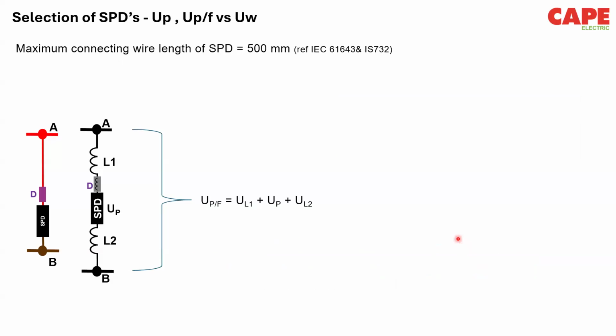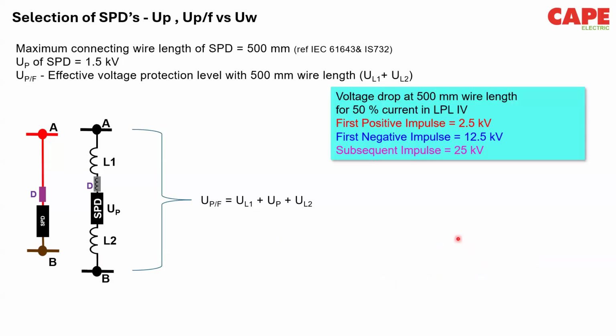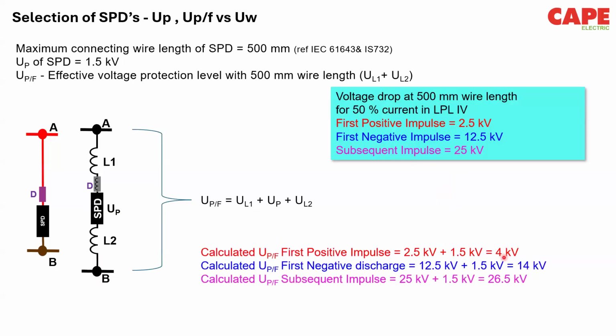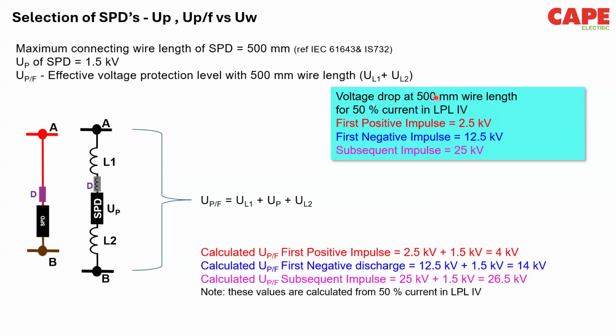Parallelly, if I consider level 4 and 50% of the current, generally for SPDs we take the LPL level and 50% of that LPL current. We get a voltage drop of 2.5 kV for the first positive impulse. For the first negative impulse, we have 12.5 kV, and the subsequent impulse is 25 kV. So when I add them together, I get 4 kV, 14 kV and 26.5 kV. This is 50% of the current in LPL level 4. Okay. Considering a 50 centimeter wire length, that is the total SPD wire length from the phase to the PE or earth connection is 50 centimeter.